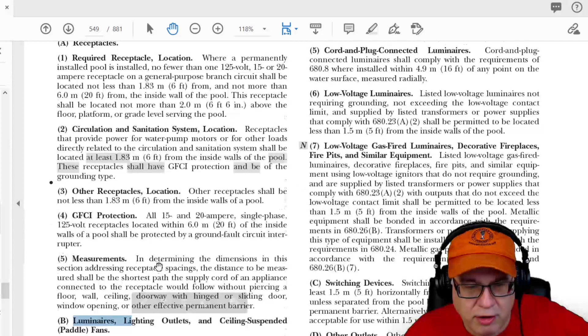So under this, I think earlier I might have said receptacles, but yeah, it's still under 22. I wasn't totally off. So remember, new installations, that was part of the question. In outdoor pool areas, extended 5 feet horizontally from the inside wall of the pool shall be installed at a height not less than 12 feet above the maximum water level of the pool.